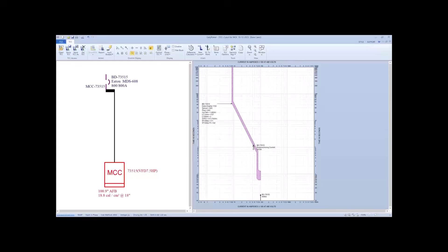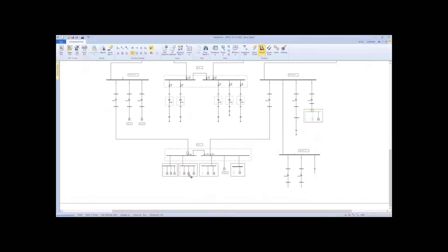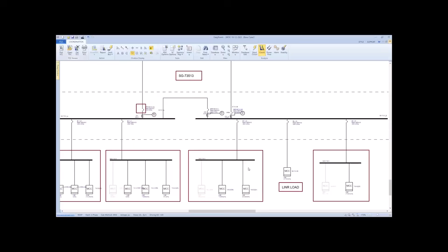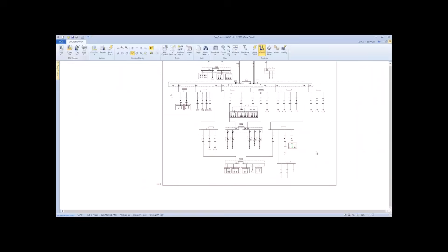I didn't know about this function. I learned it a few weeks ago, and I'm checking on all MCCs if I can improve the arc flash result by working on the TCC of the breaker, to get a better result of the arc flash. Okay. Regarding the relay coordination, Jim, what else do you think is very useful to share?